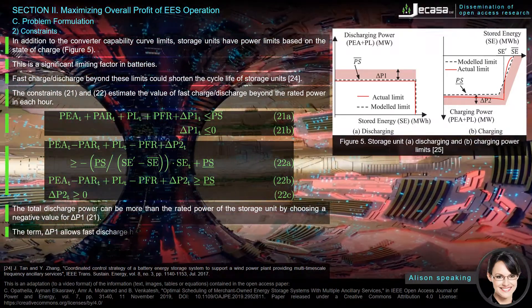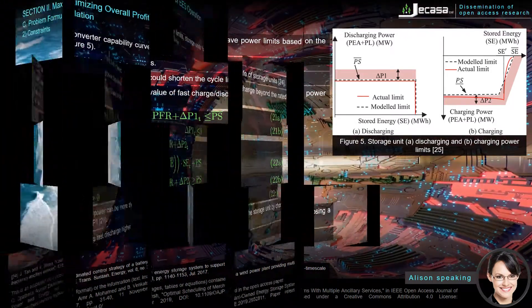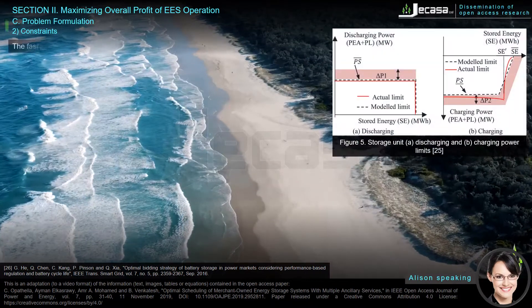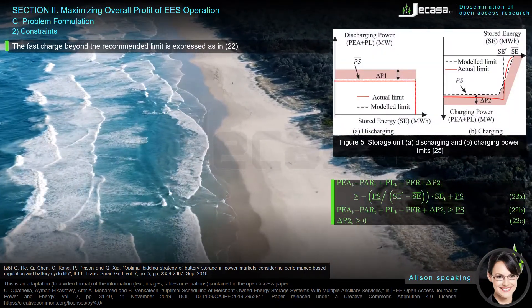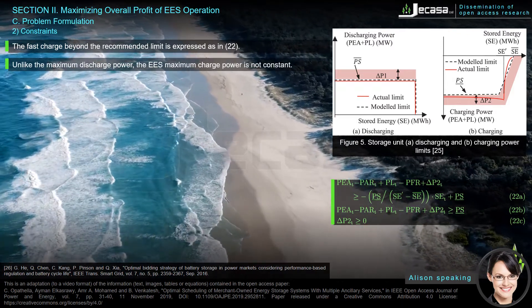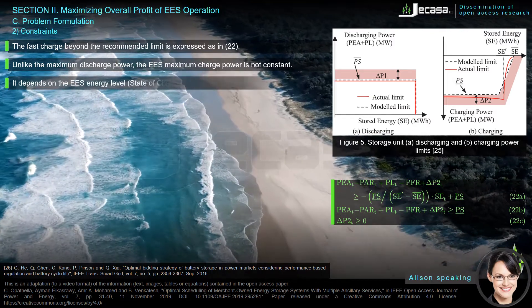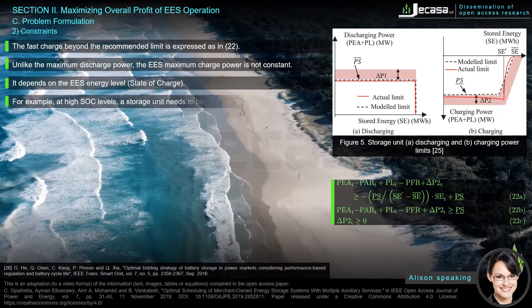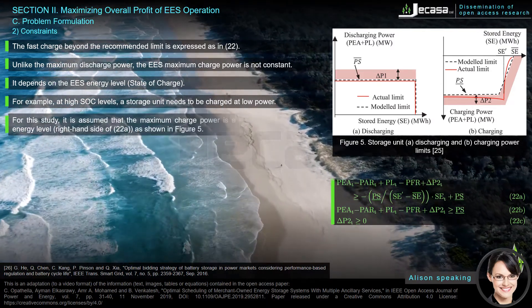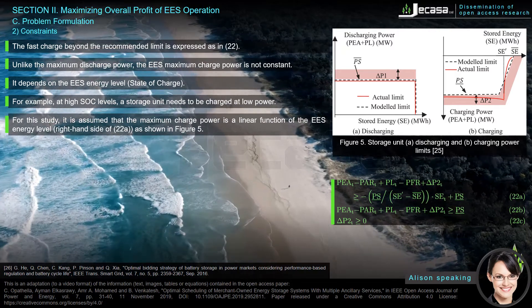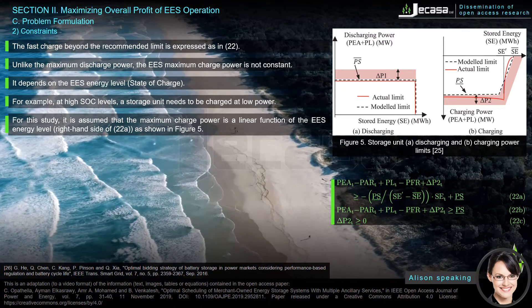The term delta P1 allows fast discharge higher than the rated power. The fast charge beyond the recommended limit is expressed in equation 22. Unlike the maximum discharge power, the EES maximum charge power is not constant — it depends on the EES energy level (state of charge). At high SoC levels, a storage unit needs to be charged at low power. The maximum charge power is a linear function of the EES energy level, as shown on the right-hand side of equation 22a and in Figure 5.